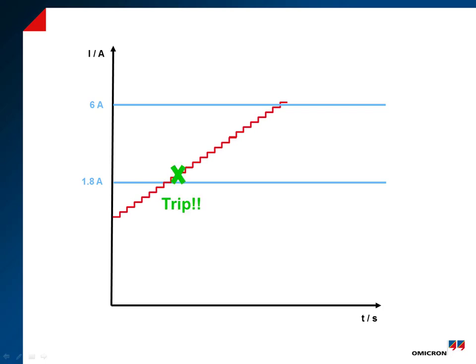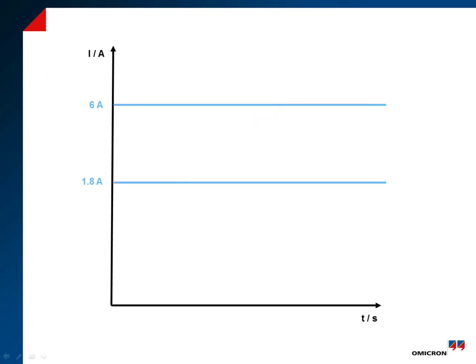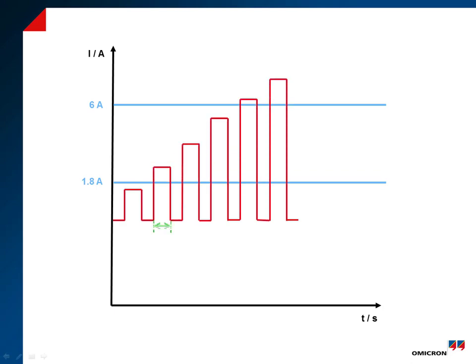By ramping the current in pulses shorter than 500 milliseconds, it is possible to prevent the first element from tripping and gradually approach the second element.